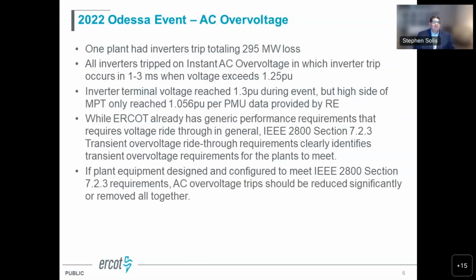Finally, AC overvoltage is another example. We had one plant that had inverters tripped totaling 295 megawatts. The inverters tripped in about 1 to 3 milliseconds when the voltage exceeded 1.25 per unit. So when we look at the POI, the voltage was well within the ride-through range. Obviously, as probably mentioned in other presentations, the terminal voltage can be quite higher than what's at the POI, and that's where the rule is.